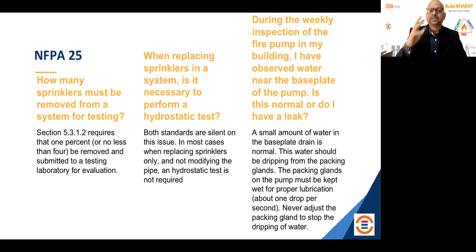These are the fundamental things that engineers should have in mind, and the codes will give clarity in terms of how the system will be monitored. Now, sprinklers are a very interesting topic, and we could go on talking about it, but the basic fundamentals are these. If a sprinkler's bulb is half filled, replace it. If the deflector is deflected or turned out, replace it. If a concealed sprinkler's cover plate is broken, replace it. If it is corroded, replace the sprinkler. If it is painted, replace the sprinkler, because you are not supposed to paint sprinklers.